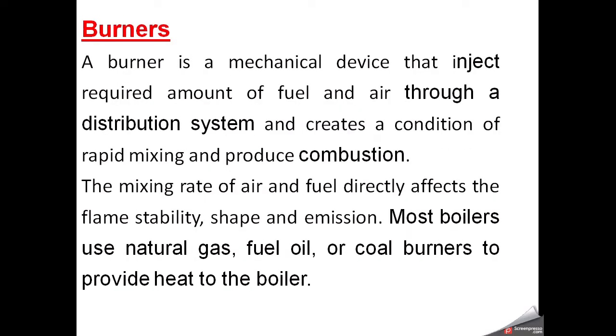A burner is a mechanical device that injects the required amount of fuel — whether coal, gas, furnace oil, or diesel — and air through a distribution system, creating conditions for rapid mixing. Fuel and air are rapidly mixed to produce combustion which generates heat. When water absorbs this heat at a certain temperature and pressure, it converts into steam. The mixing rate of air and fuel directly affects the flame stability, shape, and emission. The ratio of fuel to oxygen required to burn that fuel plays a very important role in flame stability and boiler operation.